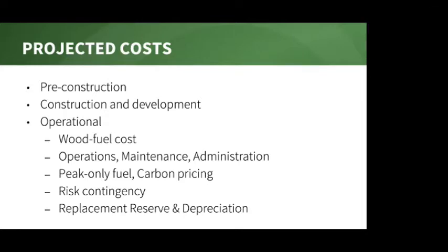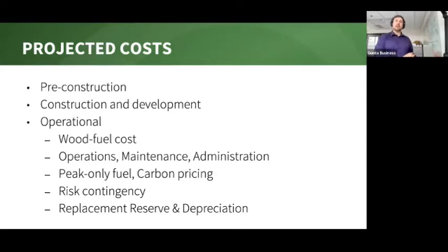It seems like a question that was born out of some of the older or late model biomass projects that I will say I've toured, a lot of the 90s into the 2000s and even the early 2000s. There was a lot of misplaced focus in the Yukon, and I'll talk about the Yukon more openly, that really set biomass back. And in a lot of these cases, they were oversized systems, singular burners that need to be at a certain output to become even efficient.